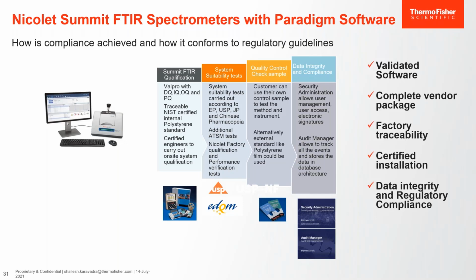Our security administration consists of two softwares. One is Security Administration and one is Audit Manager. Security Administration allows complete user management, user access, and electronic signatures, and Audit Manager allows you to track all the events and store the data in a database architecture. So we provide a fully validated software, a complete package with factory traceable standards and certified installation.